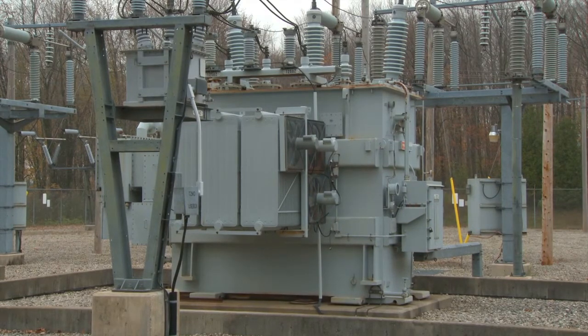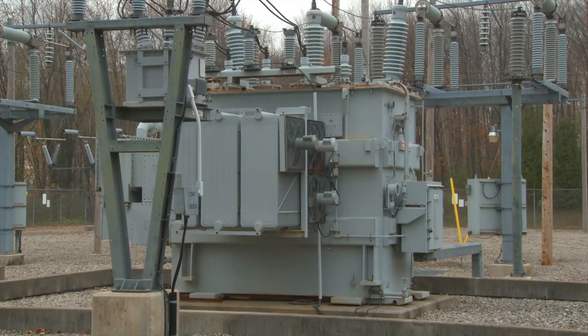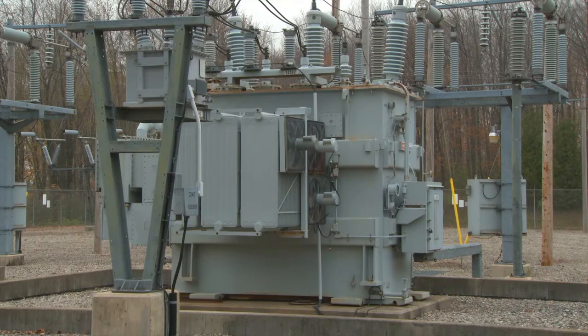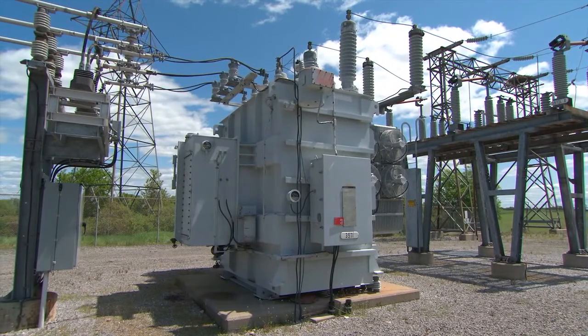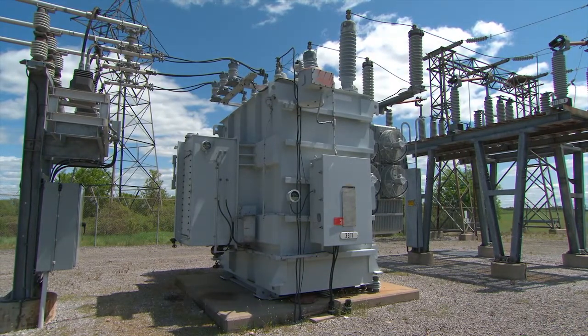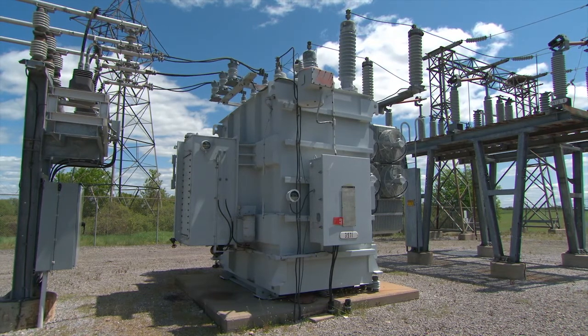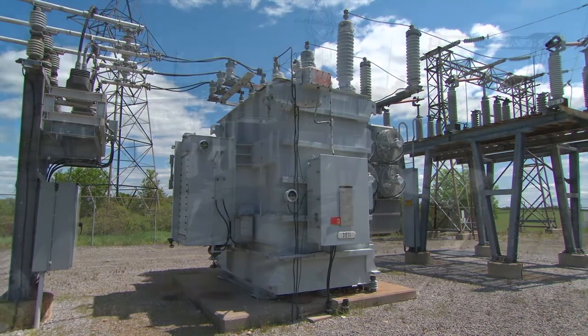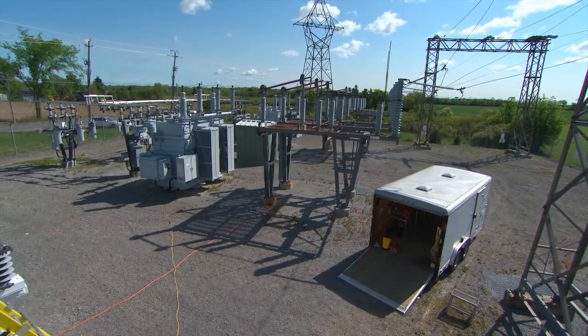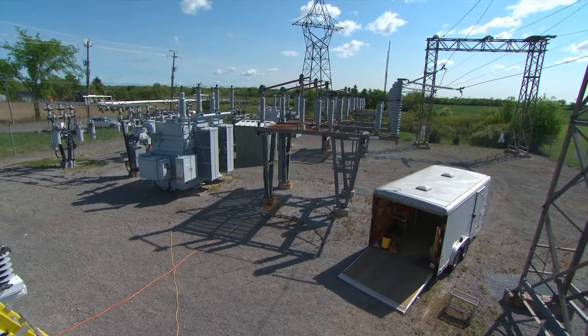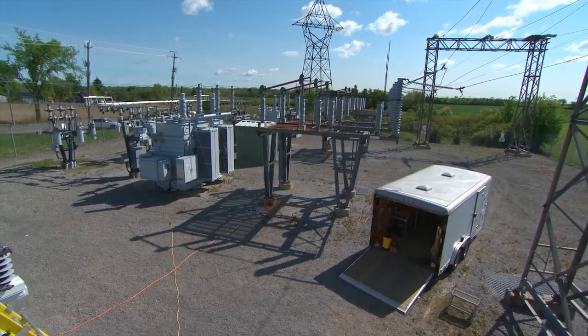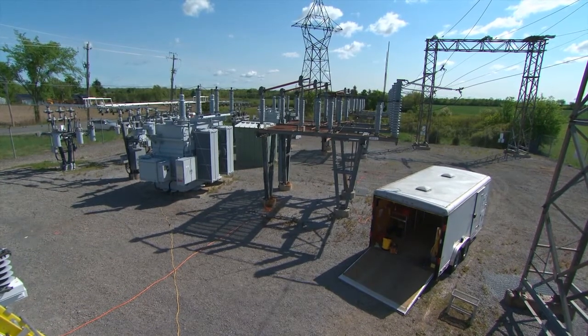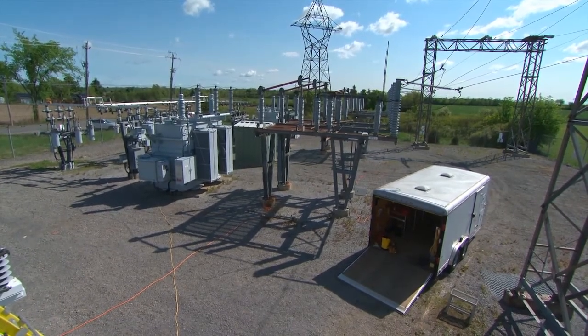Transformers are the heart of any electrical distribution system and are expensive capital items. If they fail unexpectedly, then the impact on customer service as well as system restoration can be very expensive. Transformers require several internal electrical insulation strategies to function properly. Transformer oil serves to facilitate cooling, and it also provides a high dielectric medium to prevent high voltage arcing within the transformer. The other principal insulation medium is a type of cellulose paper. A large transformer can contain many tons of this material, along with thousands of liters of transformer oil.